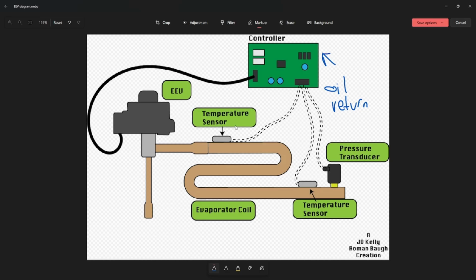It also helps ensure that on the next startup cycle, we don't slug the compressor with a big chug of oil on startup because we can't compress a liquid. Oil is a liquid. We don't want a big gulp of oil hitting the scroll plates as it's trying to pump refrigerant through it because that's going to damage the compressor. A lot of these inverter-driven systems have a dedicated oil return mode that they track based off of runtime on compressor signals. So if the compressor runs for X amount of time at X speed, then that board will calculate, okay, I'm losing this much oil per hour while I'm in this run mode, run speed.